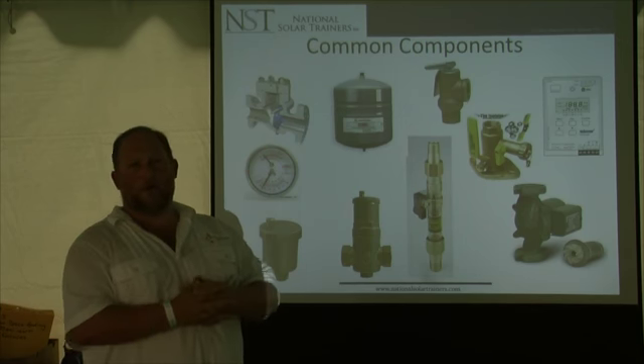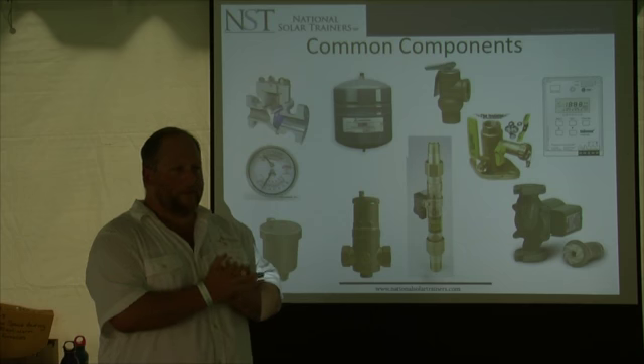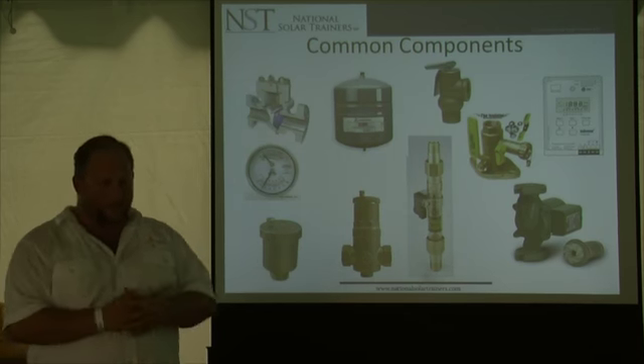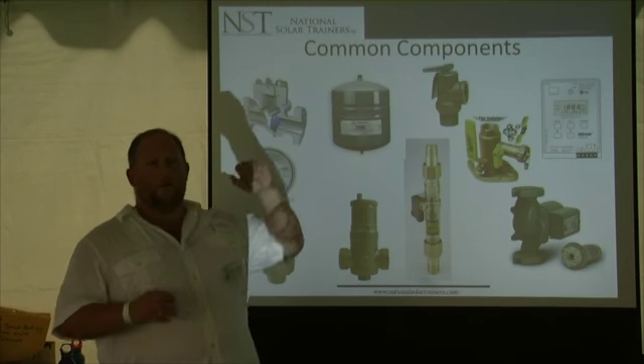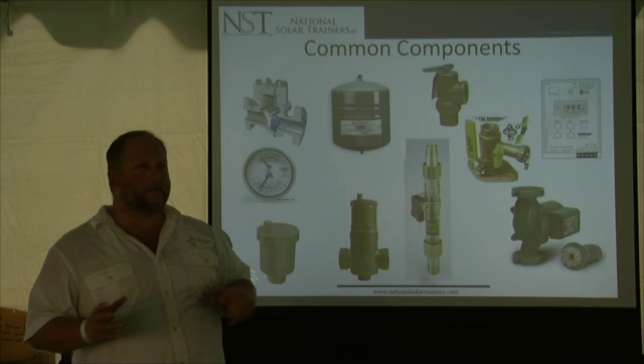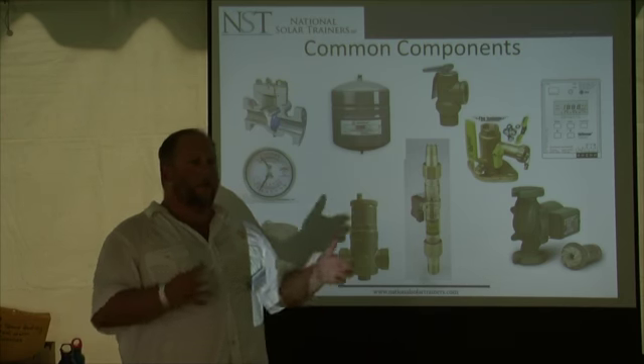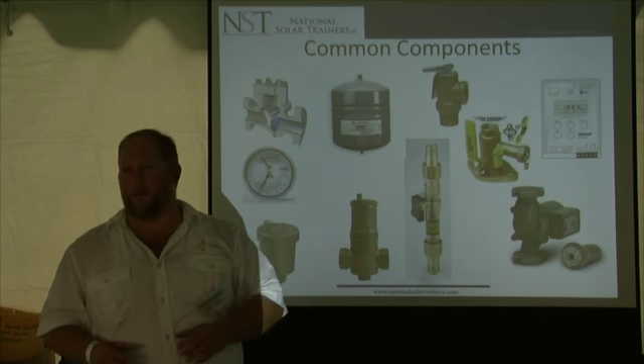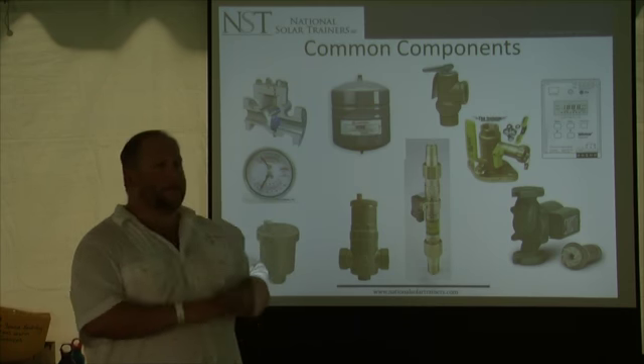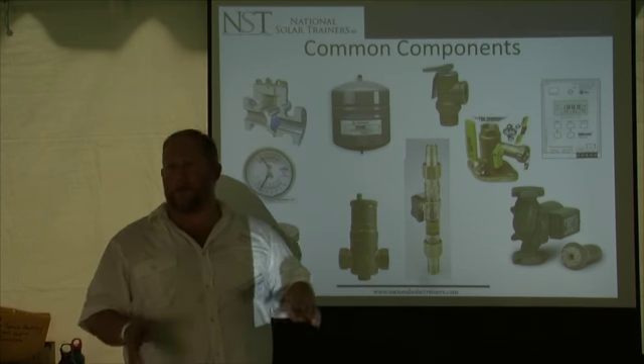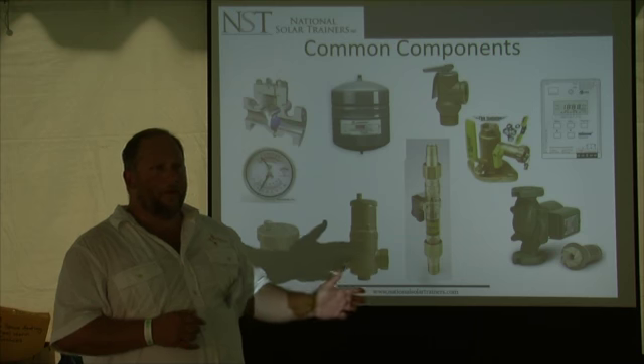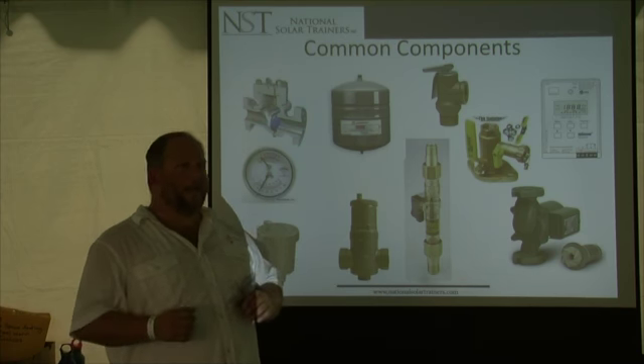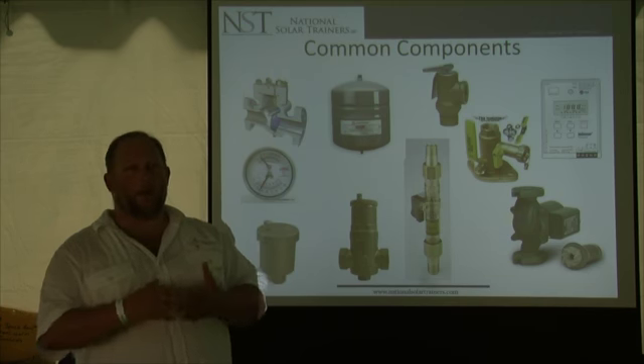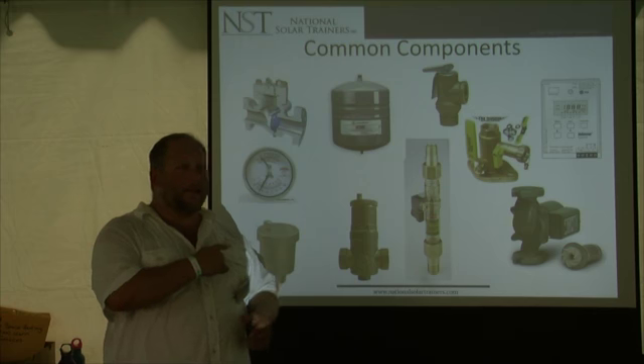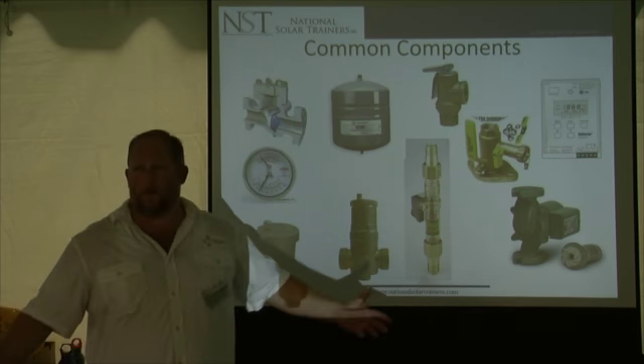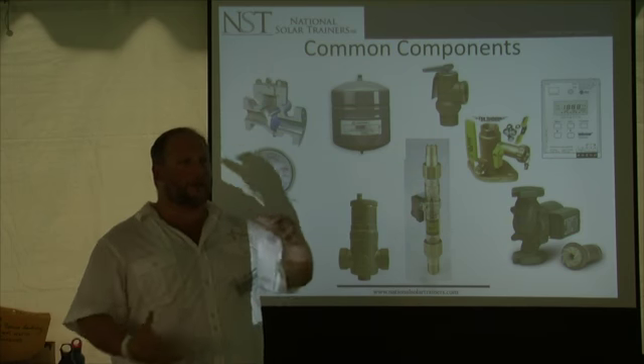There's so much that is important. It's hard to trim out what you don't want to know because you want to understand the big picture, right? The placement of where that expansion tank goes in the loop makes a huge difference. A boiler installer puts the expansion tank behind the pump, but the expansion tank serves a completely different purpose with thermal than it does with boiler hydronics. The expansion tank helps to pressurize the pump so it doesn't cavitate. We don't have that problem. We're operating at high pressure anyway. What we need that expansion tank for is when the collector begins to overheat. The volume has to enter the expansion tank.